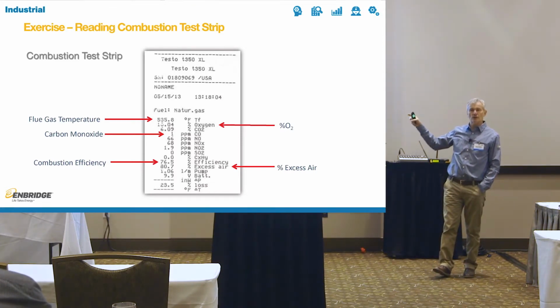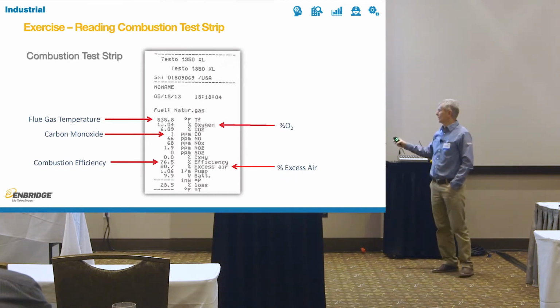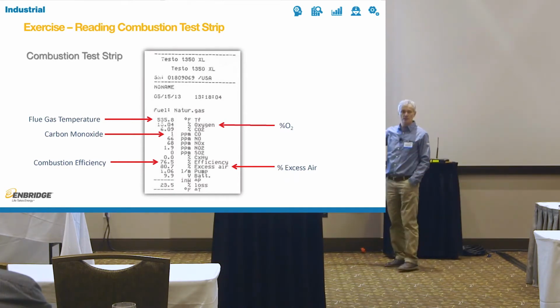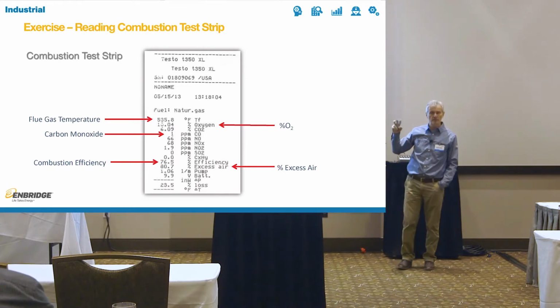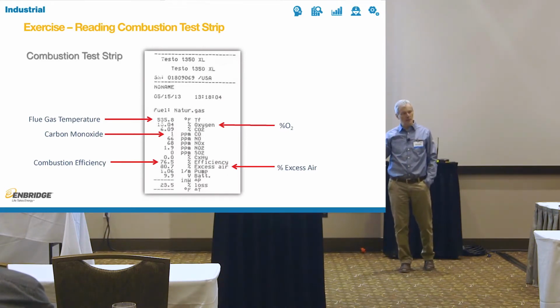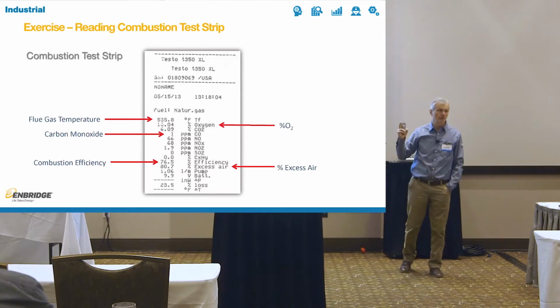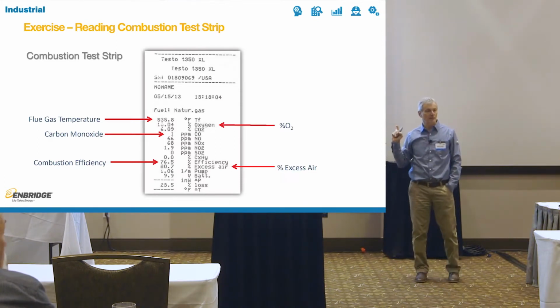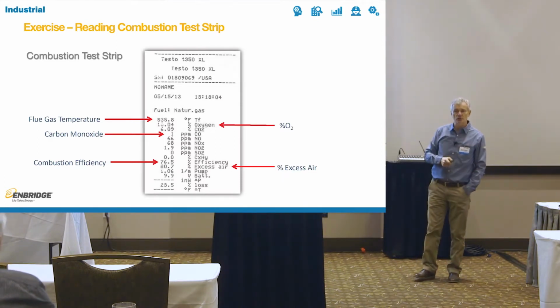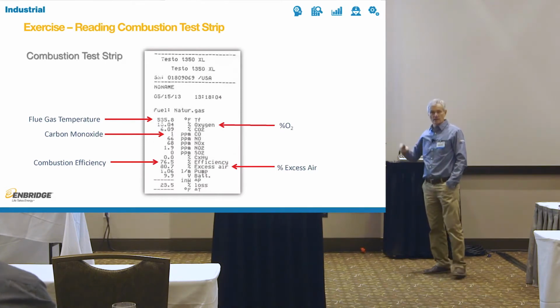Most of them are not that well calibrated, and most of them will be off. Depending on how complicated their algorithm is to calculate efficiency, you will get sometimes close, sometimes widely different numbers, but never the same. So I wouldn't rely on that as gospel to say this is what my efficiency is. I would look at the other factors.